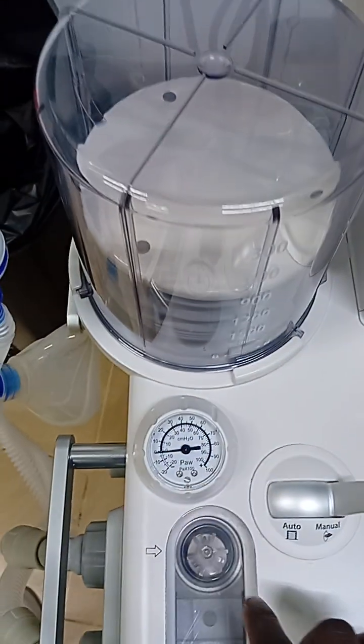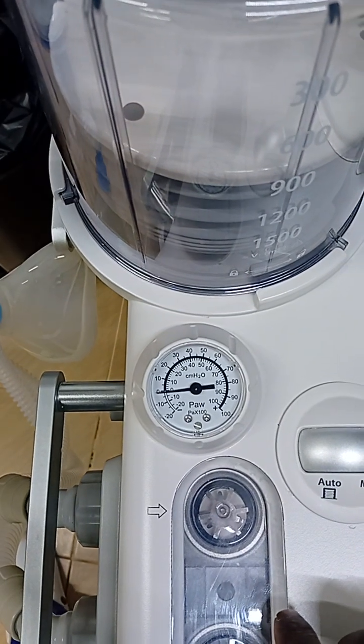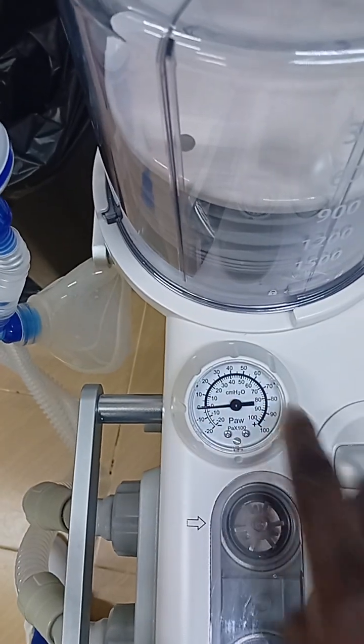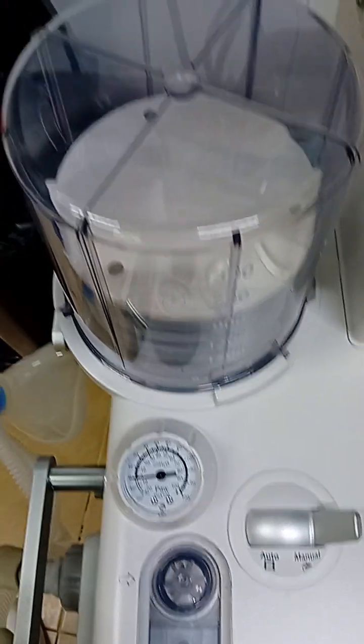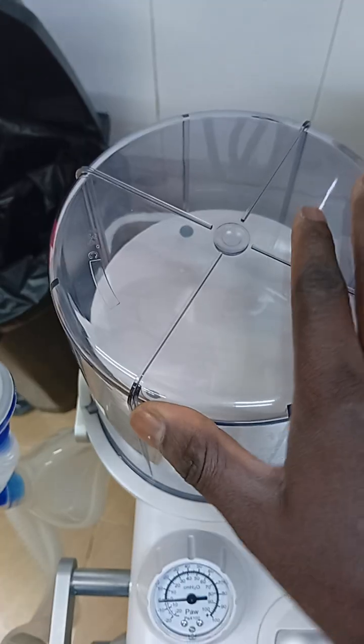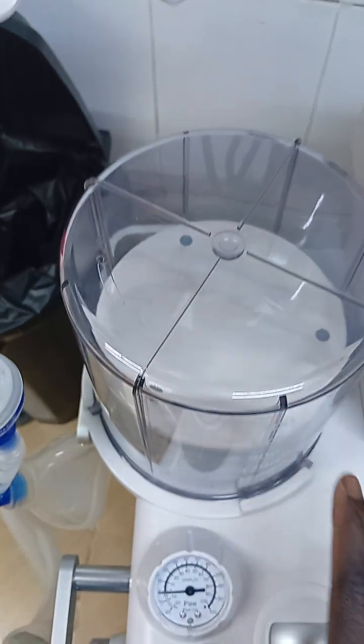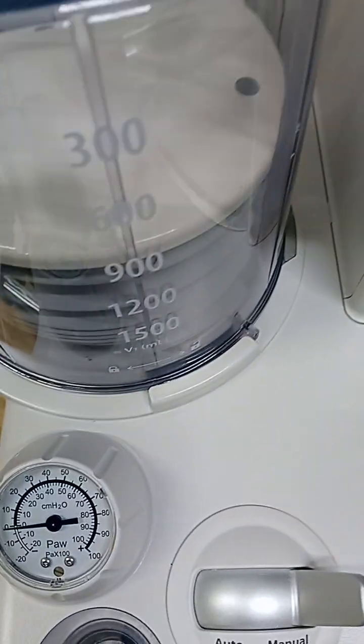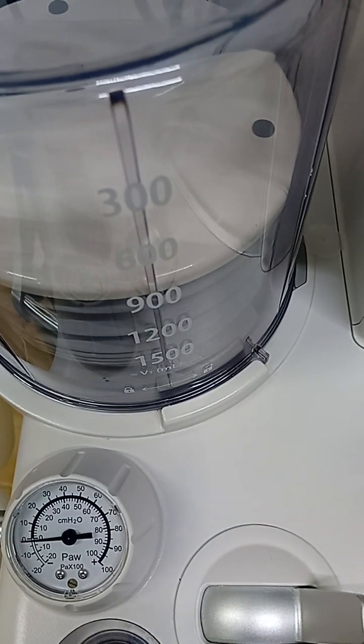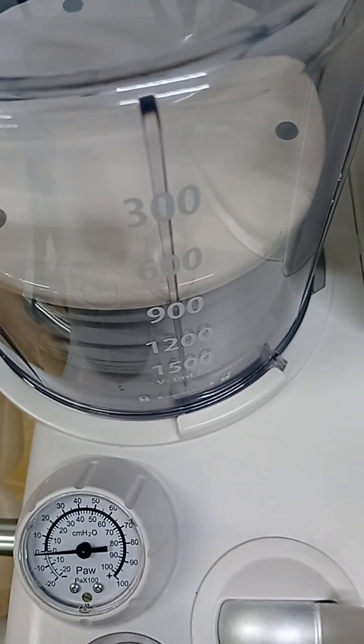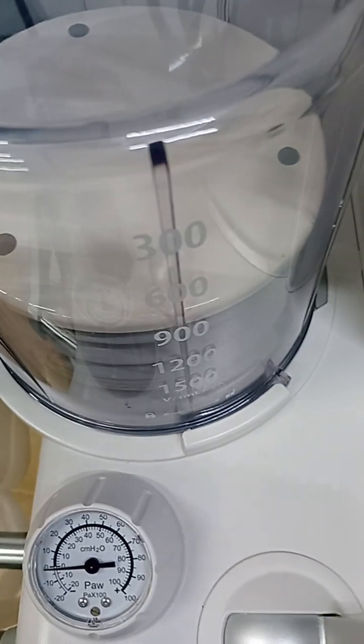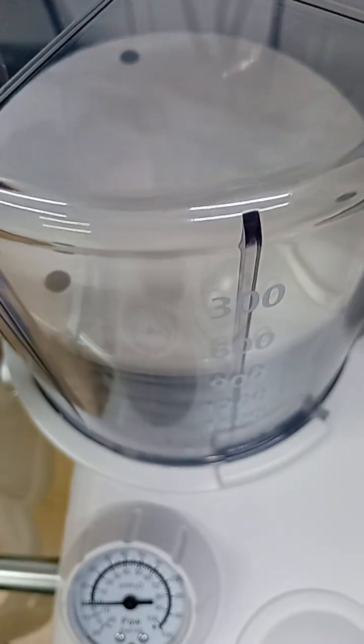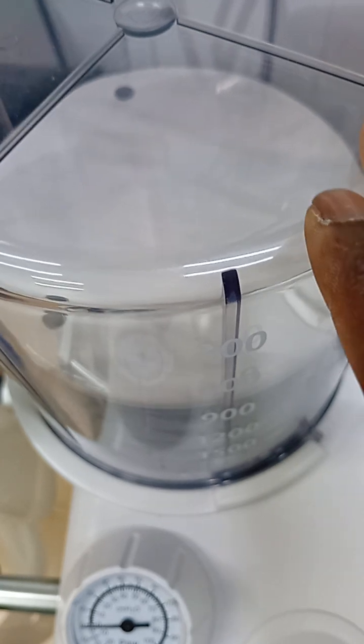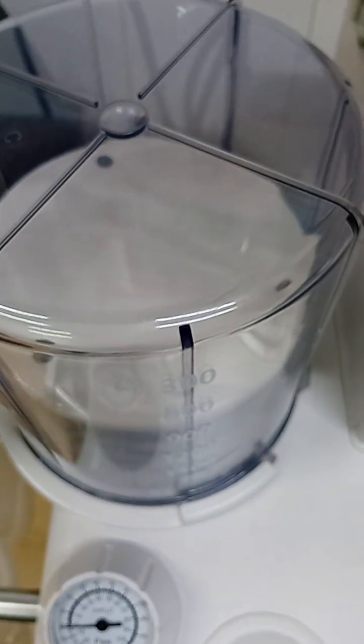Of course, here we have what we call a reservoir bag. Next to the reservoir bag we have this pressure gauge. It checks the airway pressures. It will be indicating as you are ventilating your patient. This one is called the bellows. When the patient is being ventilated, the bellows will be moving up and down, and as you can see on the side, it indicates it is well calibrated, and the bellows will move to the depth of the settings that you set on the ventilator, how much volume you want to ventilate your patient.